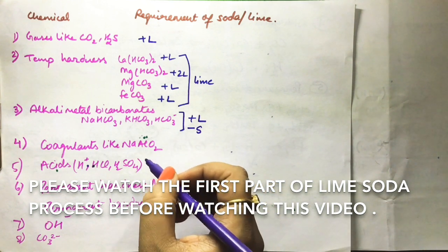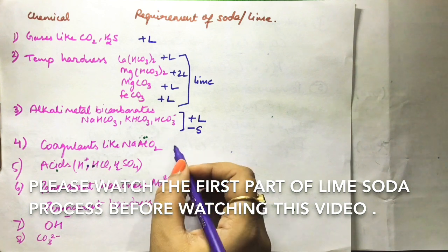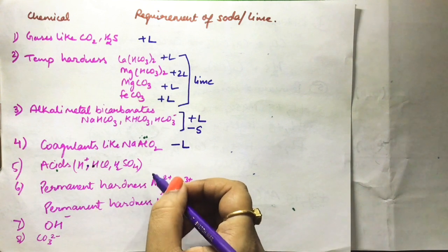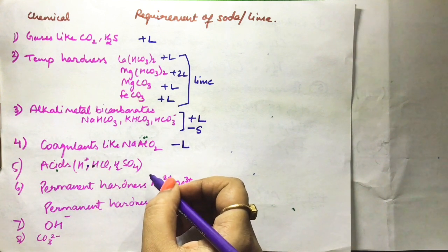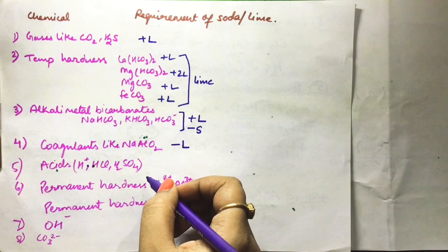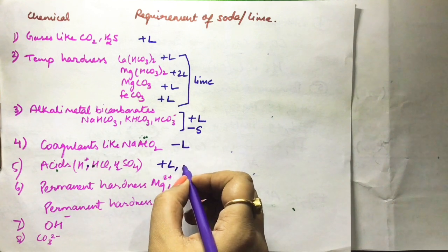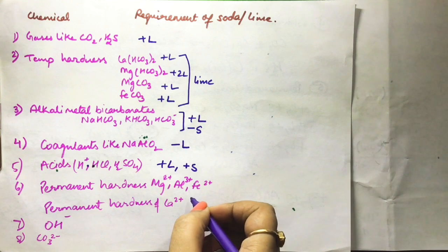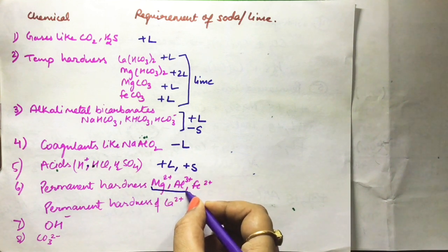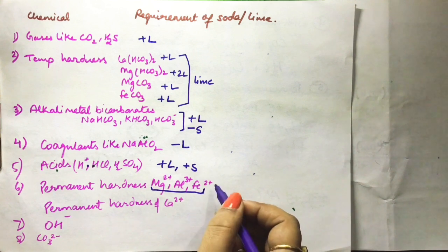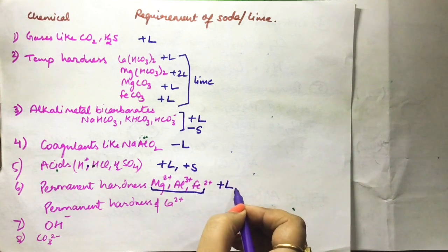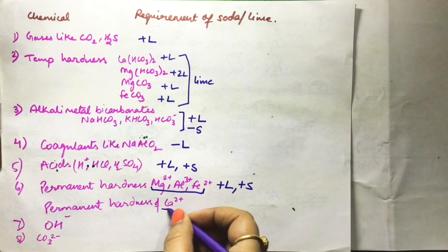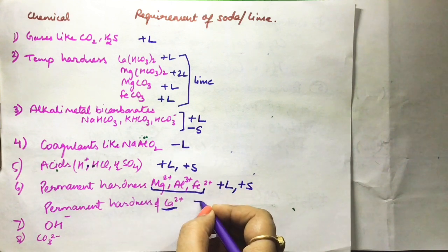NaAlO2 sodium aluminate coagulant — we have seen its reaction, lime is subtracted for acids; acids require plus lime and plus soda. Permanent hardness by magnesium, aluminum, and iron requires lime and soda. Permanent hardness of calcium requires only soda.